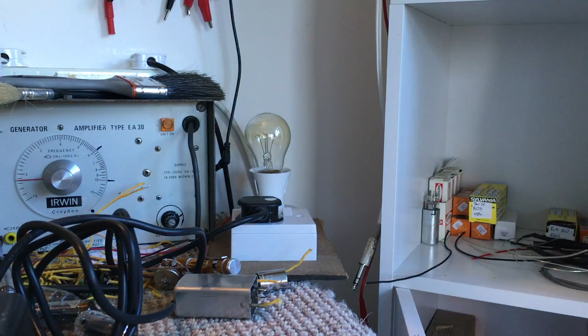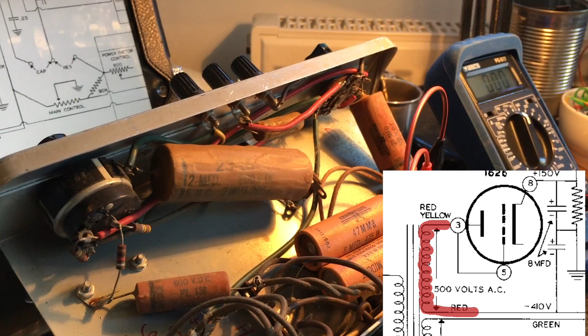Right, carry on. So I've now made the connections to the red and red yellow, the 500 volt winding, like we did earlier. We're still measuring AC, 600 volt range. Just let that sort itself out. So this is our red to red yellow, and we're looking for 500 volts. I do expect a tiny bit more, but we'll see. 3, 2, 1.